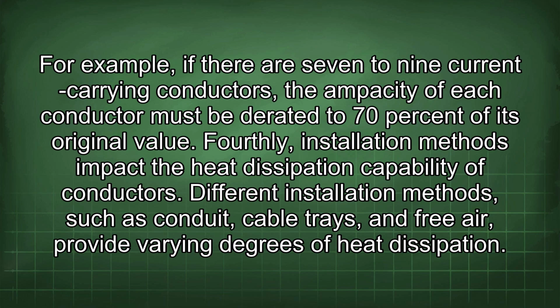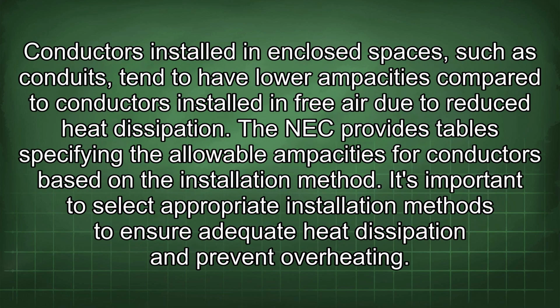Fourthly, installation methods impact the heat dissipation capability of conductors. Different installation methods such as conduit, cable trays, and free air provide varying degrees of heat dissipation. Conductors installed in enclosed spaces, such as conduits, tend to have lower ampacities compared to conductors installed in free air due to reduced heat dissipation. The NEC provides tables specifying the allowable ampacities for conductors based on the installation method. It's important to select appropriate installation methods to ensure adequate heat dissipation and prevent overheating.